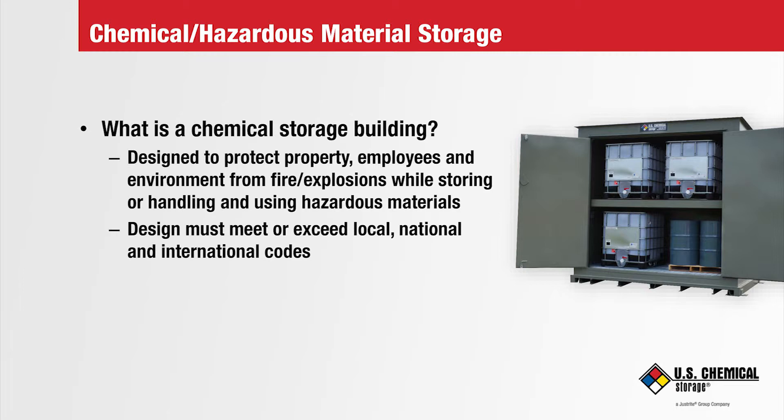These codes have limited the total footprint of a chemical building not to exceed 1,500 square feet. Yet the largest one ever built was 3,182 square feet per floor, shipped in 24 modules for the General Motors Power Train Division. This was due to the relationship the user had with the local authorities, and they were self-insured. It was utilized for testing large truck engines and their transmissions.